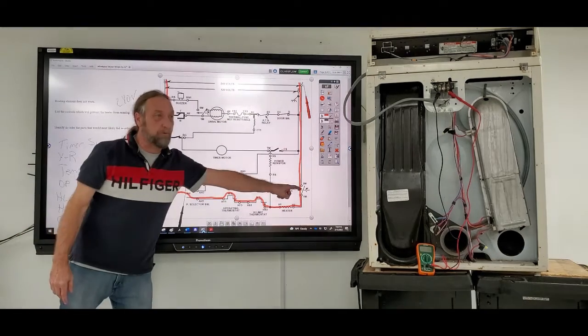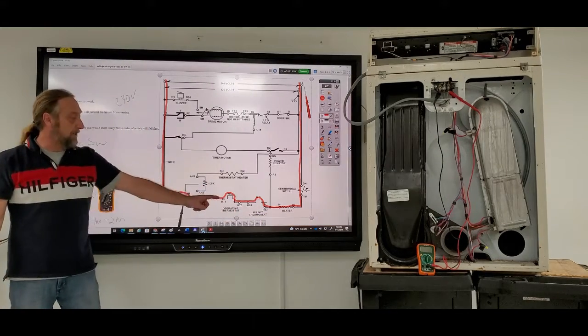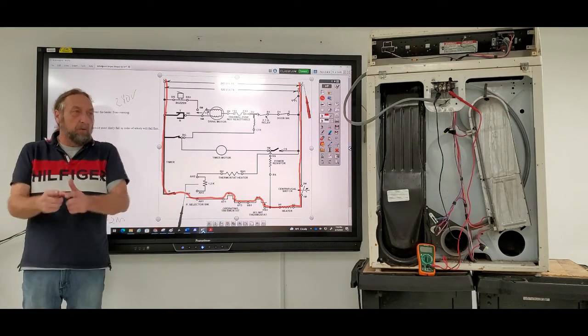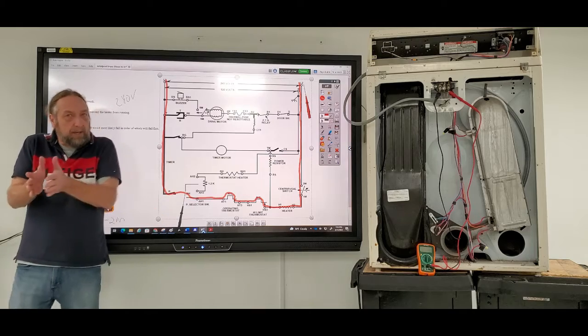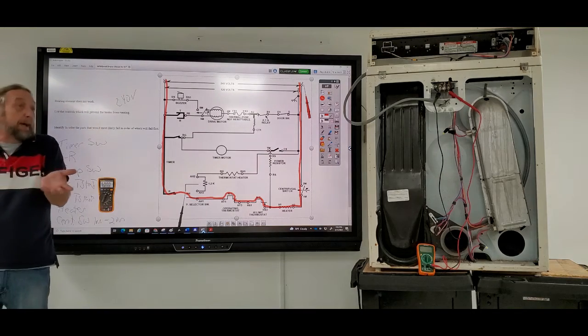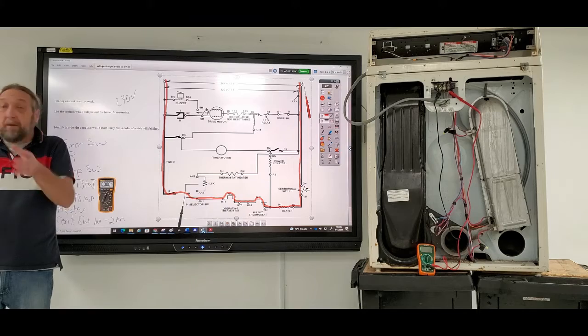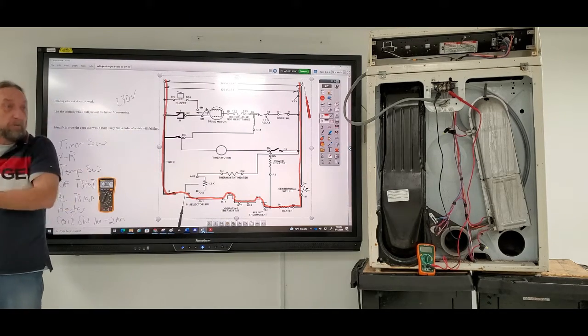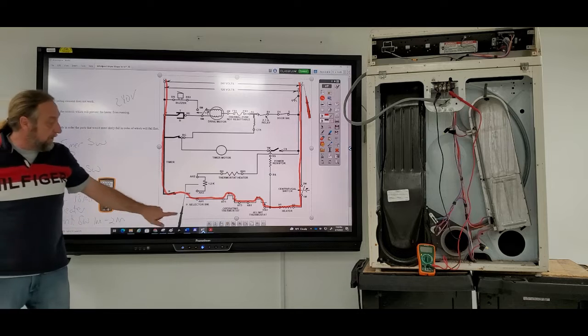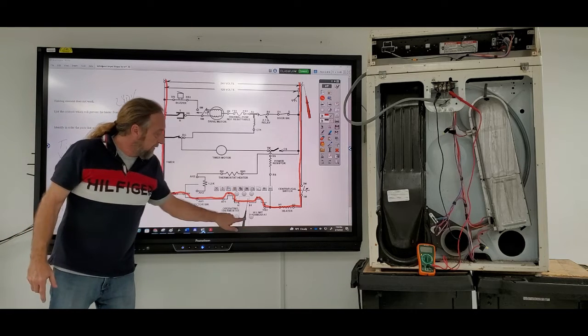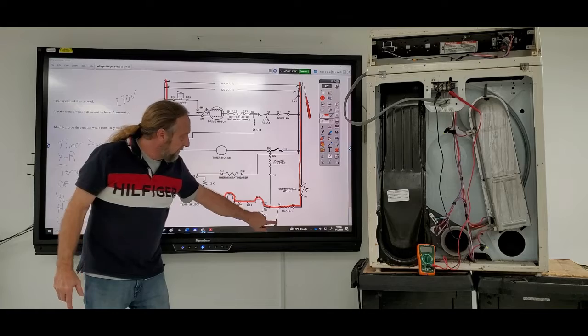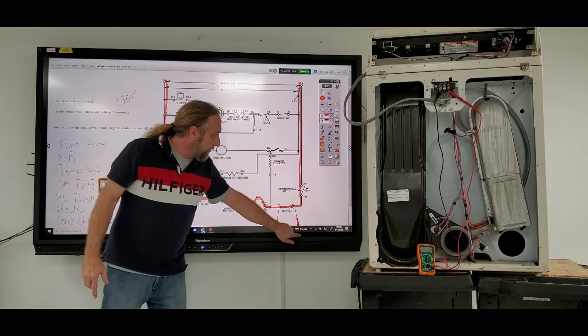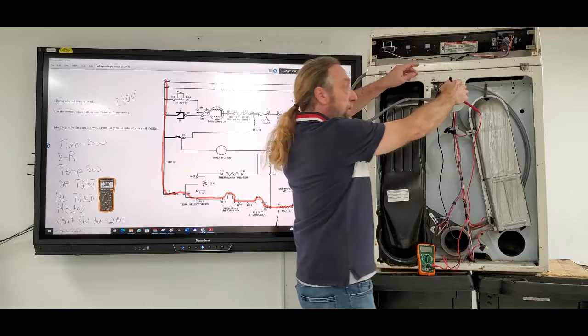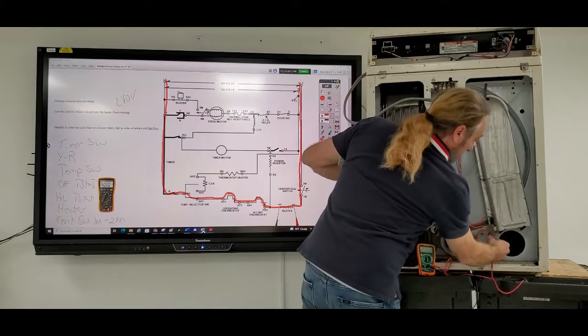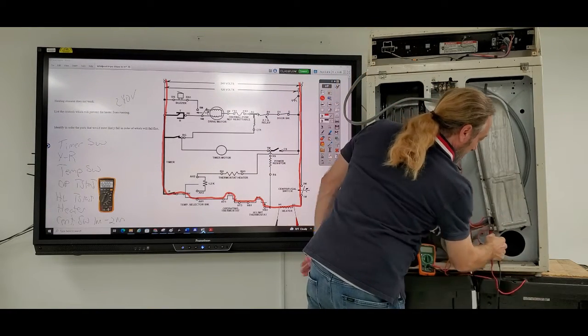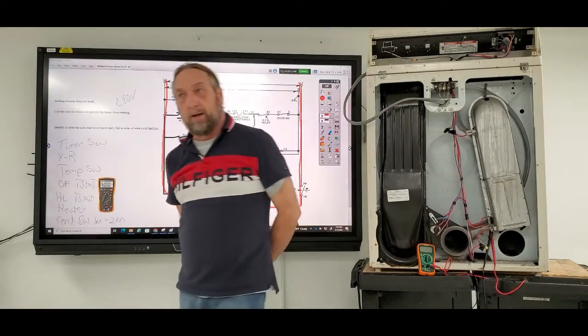I still have a centrifugal switch, the heating element, that thermostat, and the selector switch. In other words, I'm not really narrowing it down, so to speak. I'm in the middle of the circuit trying to say, well, do I go left or right? So what I do is I go to the heater, here, and here to see if I have voltage. So now I take these two from the power supply and I go to both sides of the heater and say, do I have 240 there?